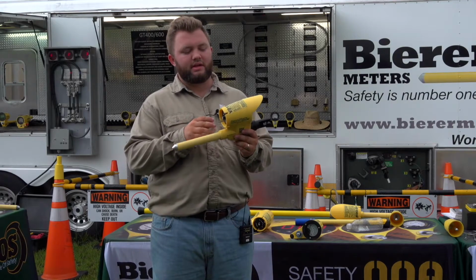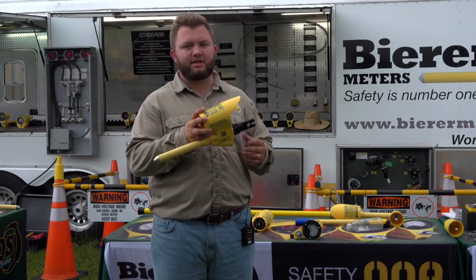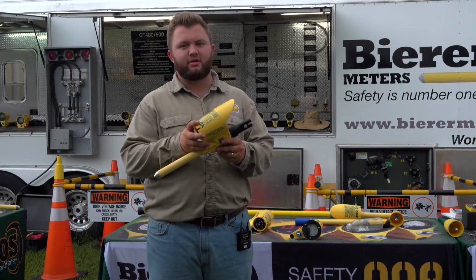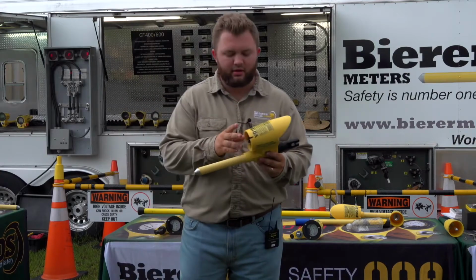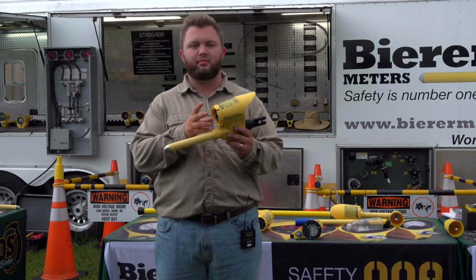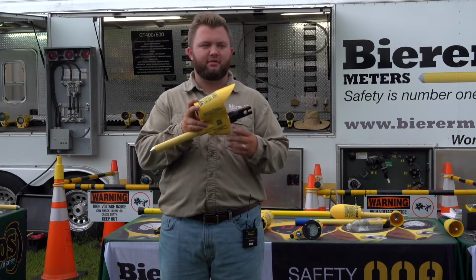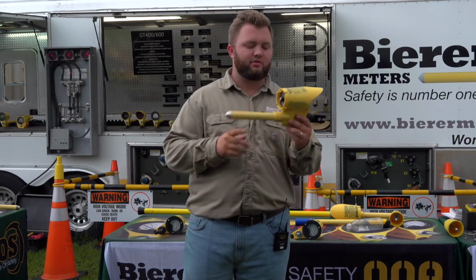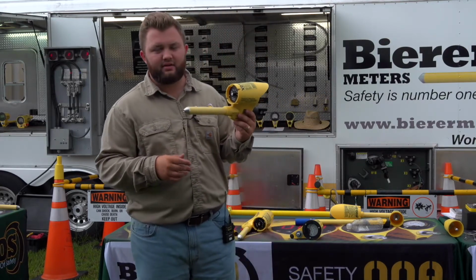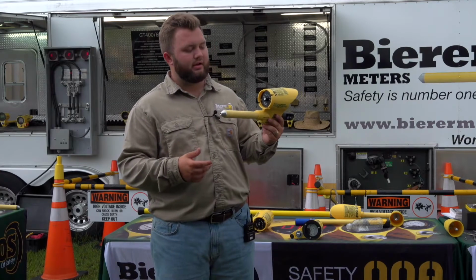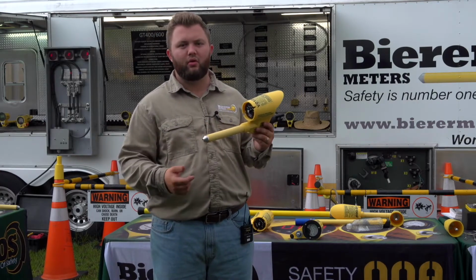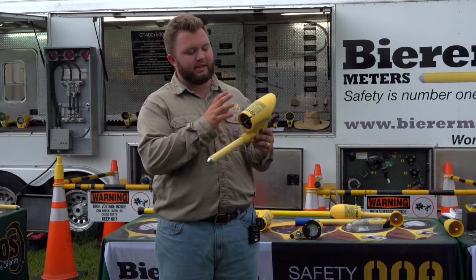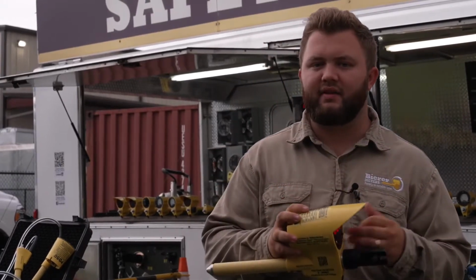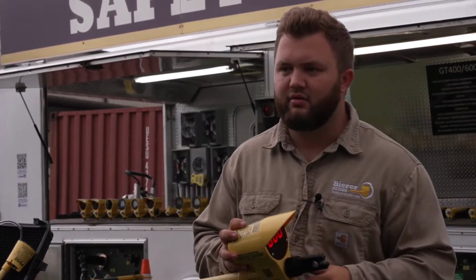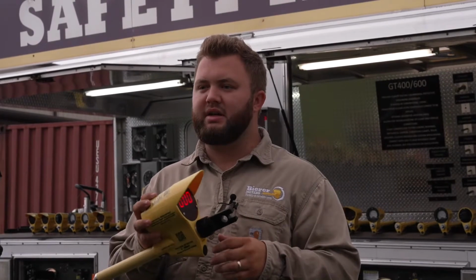The tool is going to look at the current in relation to the ground plane. So those conductive components are going to look at the current through the probe, through the meter housing in relation to ground. If the tool's wireless, it has to do that wirelessly through the air. If you've got a cord, through a cord. But again, these components inside the device are conductive, so those components become energized.